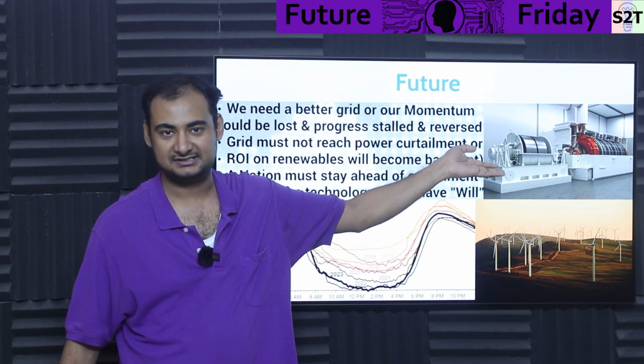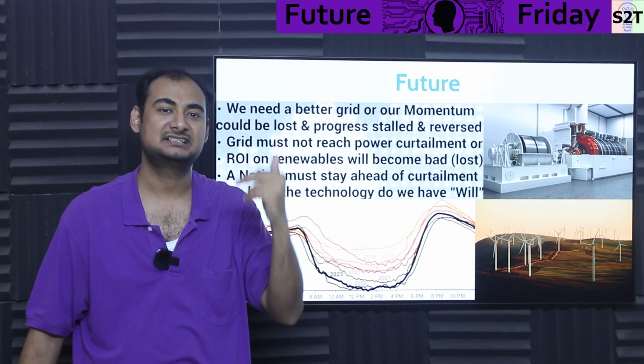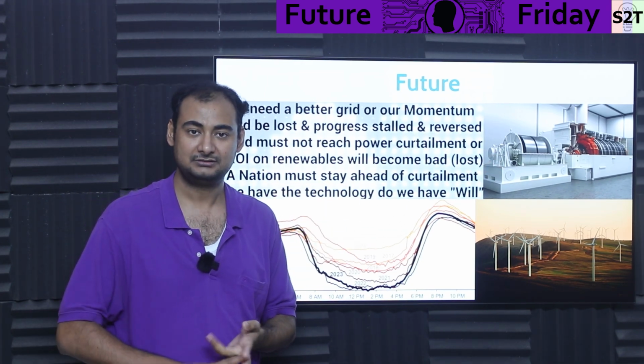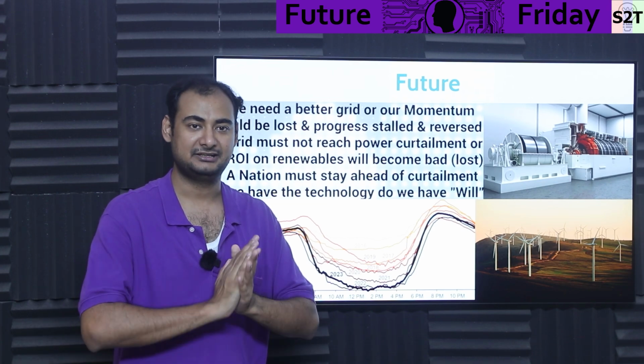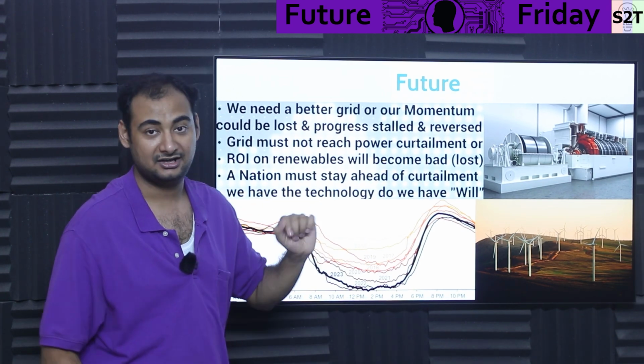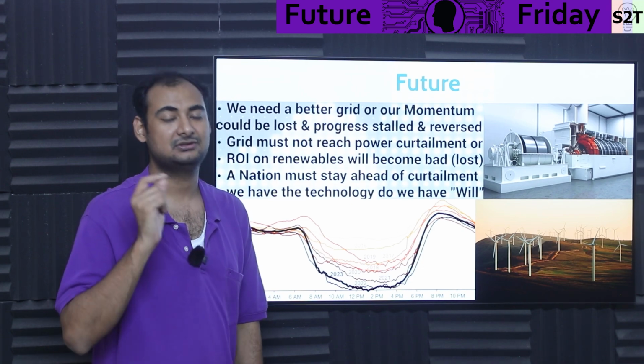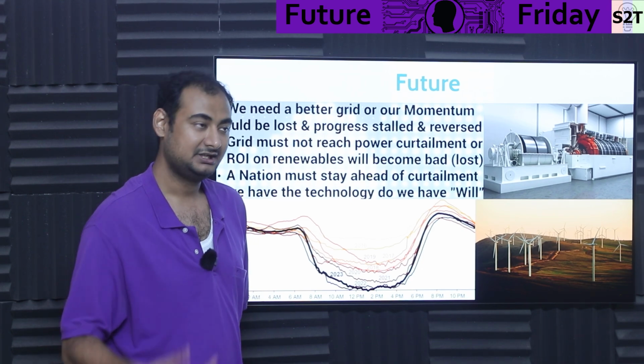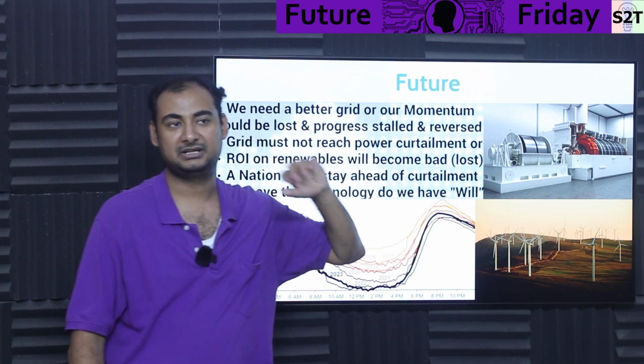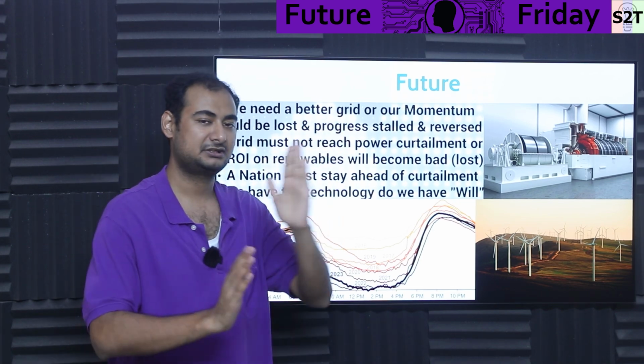They put it there. Now what does this become? This becomes what we call a synchronous condenser. So they run it like a motor, match the frequency they need to, and then done. This puppy now not only provides you inertia, it also provides power factor correction. Controlling the rotor current, they can be like, okay, positive power factor, negative power factor, they can control it.